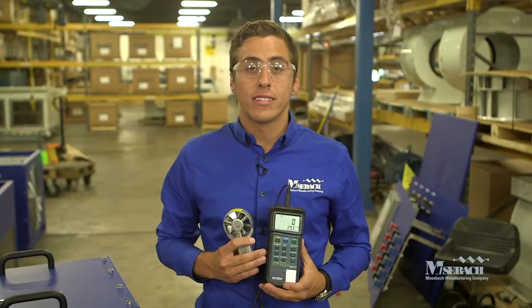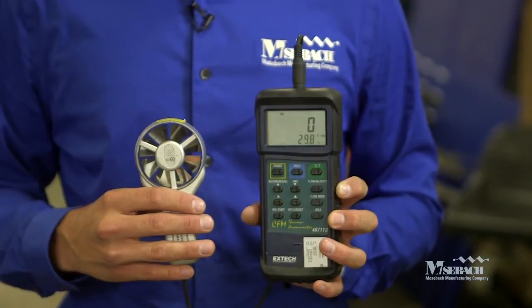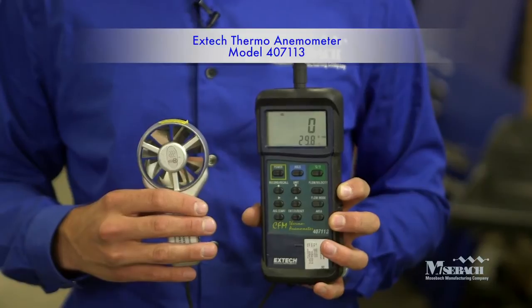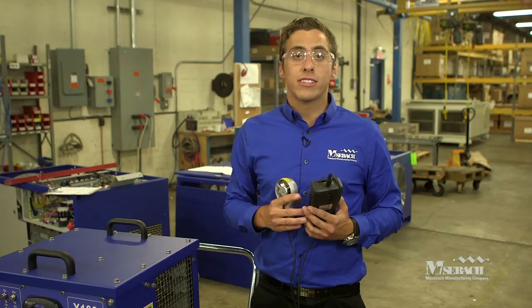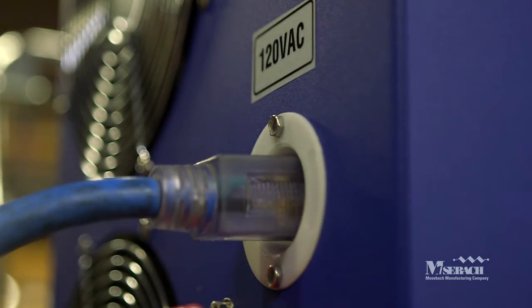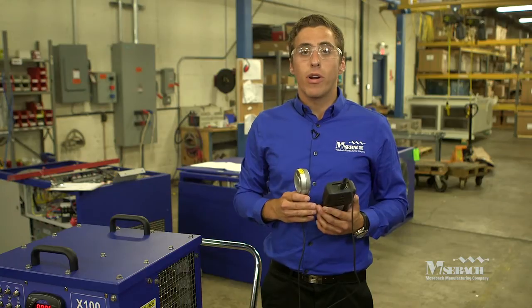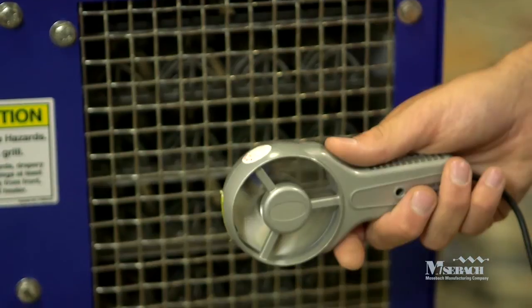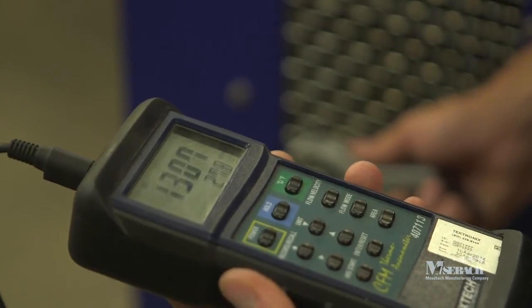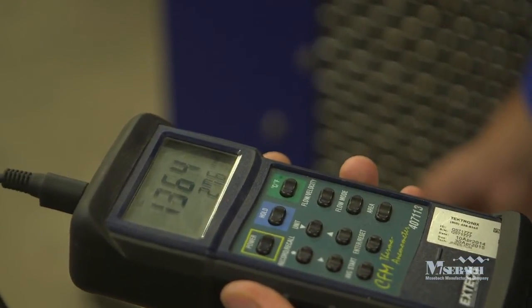Next, we're going to test the airflow to ensure that the fans are in proper working order. We recommend using the Extech Thermo Anemometer 407113. To conduct this test, you need to have the ground connected as well as the 120 volt power, and place the main switch in the on position. It is important to take a measurement behind each of the three fans. Each fan should have a minimum air velocity of 1000 feet per minute. When taking the measurements, make sure the anemometer has proper orientation towards the fan.